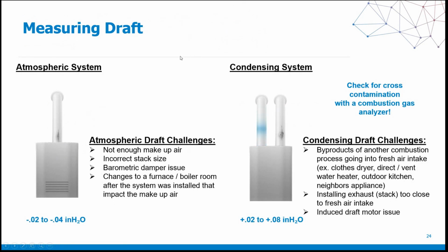So measuring draft. When we talk about draft, we have two different types of systems. We have an atmospheric system and we have a condensing system. Both systems measure draft in inches of water column. For an atmospheric system, the measurement is -0.02 to -0.04 inches of water column. In a condensing system, it is +0.02 to +0.08 inches of water column. In both instances, that is basically akin to the little combustion fairy that I showed you in the beginning. It's akin to that little combustion fairy gently breathing on the back of your neck. And I know that sounds very creepy, but that is what it feels like.